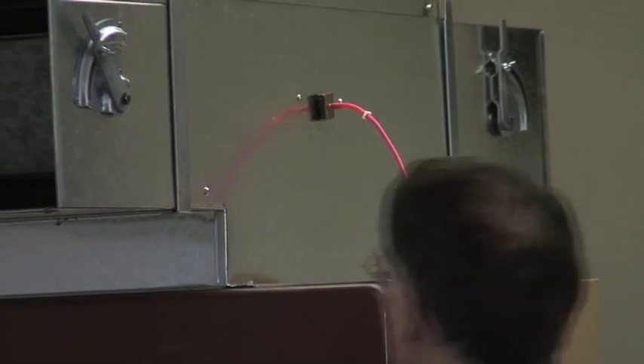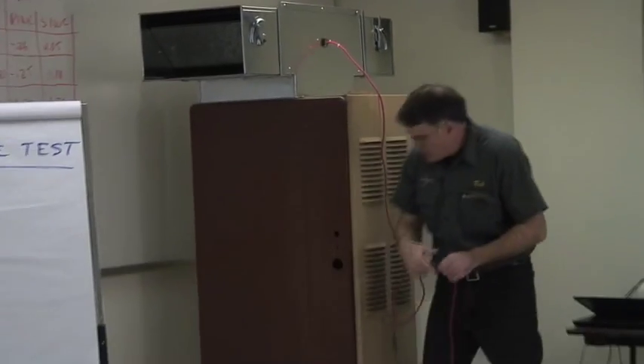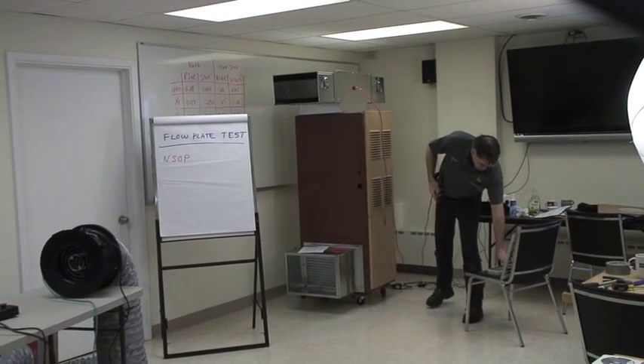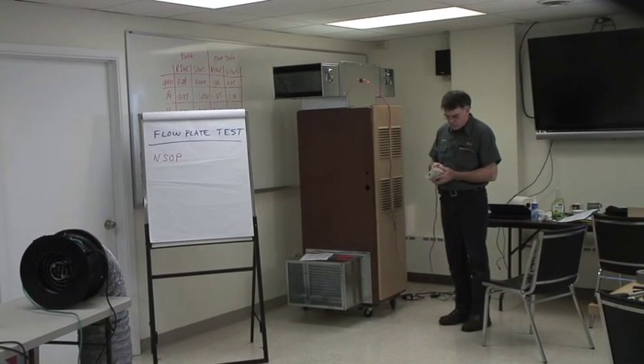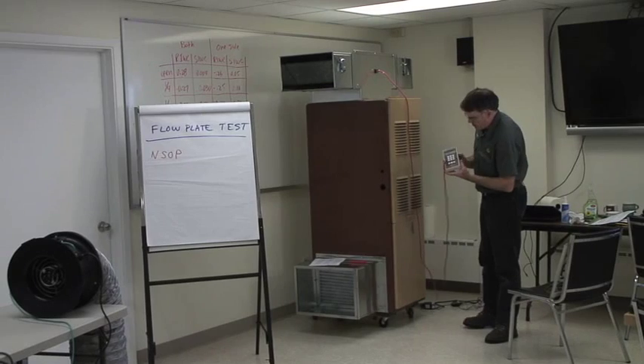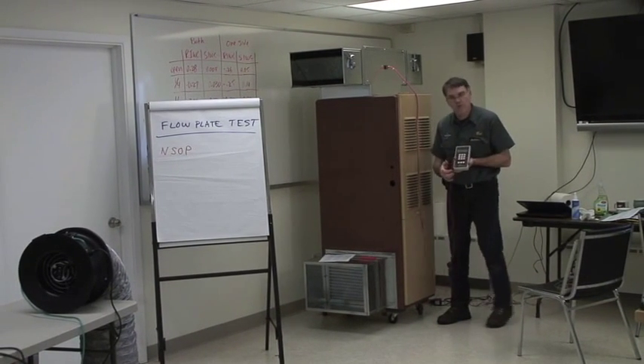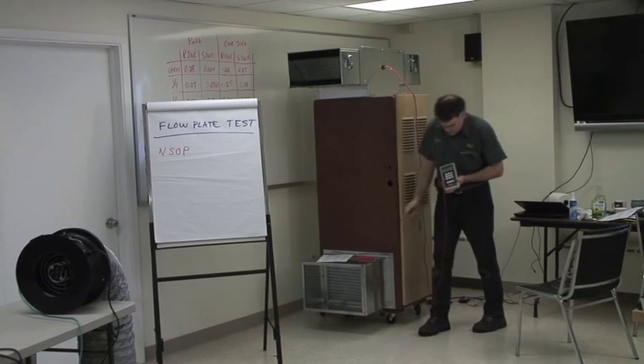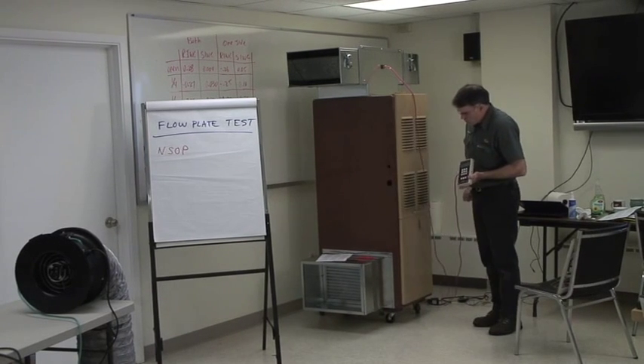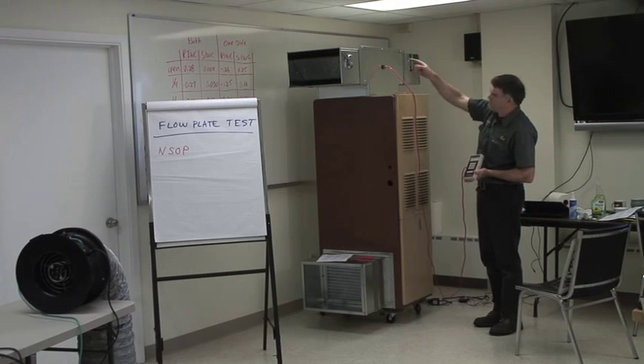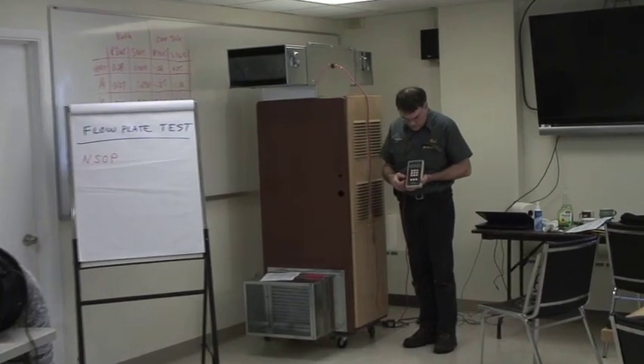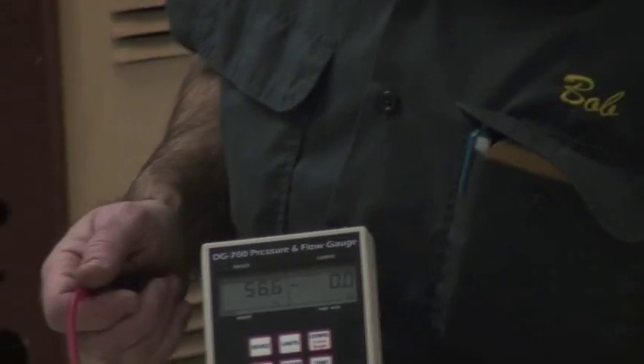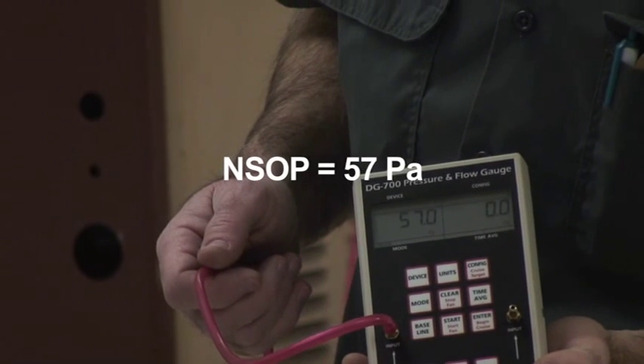This is just with our standard filter in, as though we weren't going to actually do any additional testing. We're going to hook up our pressure tap to our gauge. Turn it on. Conventionally just go on the input side with this gauge, on the A side I should say. We have our air going in and coming out the top, and we have an NSOP of about 57 Pascals.